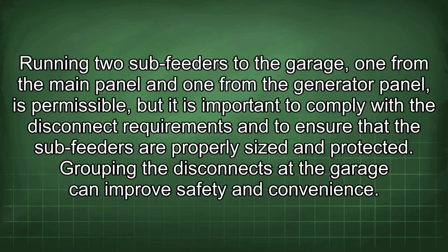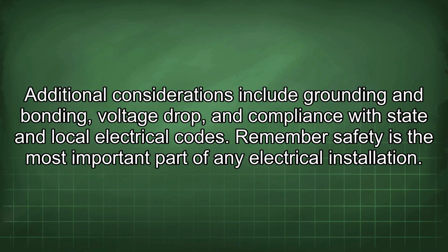Running 2 sub-feeders to the garage, one from the main panel and one from the generator panel, is permissible, but it is important to comply with the disconnect requirements and to ensure that the sub-feeders are properly sized and protected. Grouping the disconnects at the garage can improve safety and convenience. Additional considerations include grounding and bonding, voltage drop, and compliance with state and local electrical codes. Remember, safety is the most important part of any electrical installation.